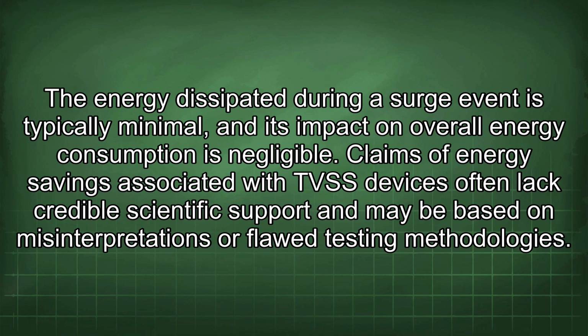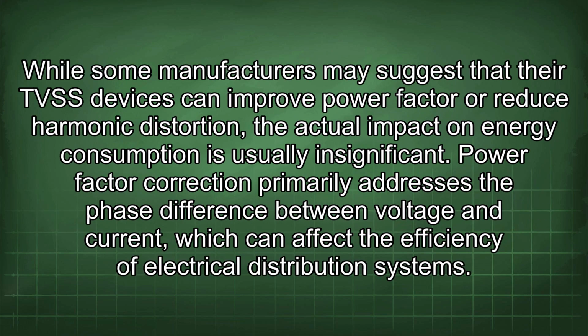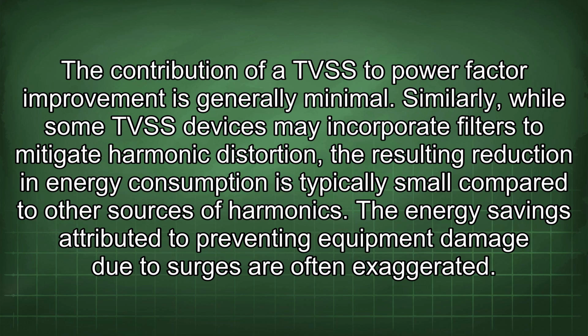Claims of energy savings associated with TVSS devices often lack credible scientific support and may be based on misinterpretations or flawed testing methodologies. While some manufacturers may suggest that their TVSS devices can improve power factor or reduce harmonic distortion, the actual impact on energy consumption is usually insignificant. Power factor correction primarily addresses the phase difference between voltage and current, which can affect the efficiency of electrical distribution systems. The contribution of a TVSS to power factor improvement is generally minimal. Similarly, while some TVSS devices may incorporate filters to mitigate harmonic distortion, the resulting reduction in energy consumption is typically small compared to other sources of harmonics.